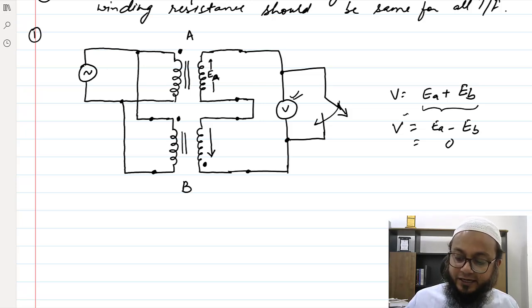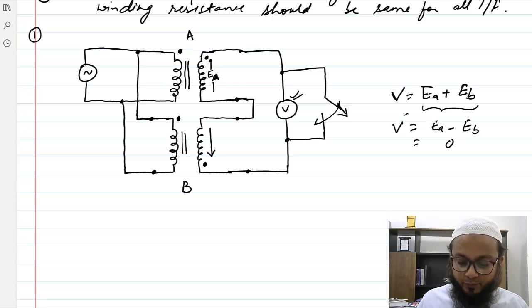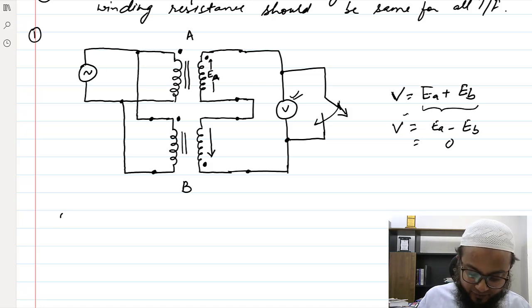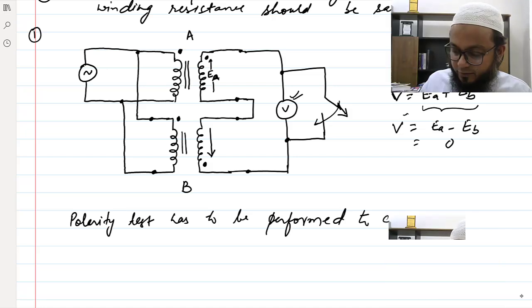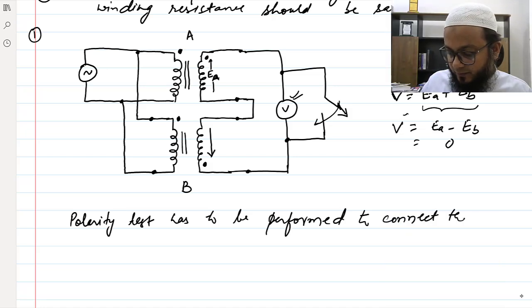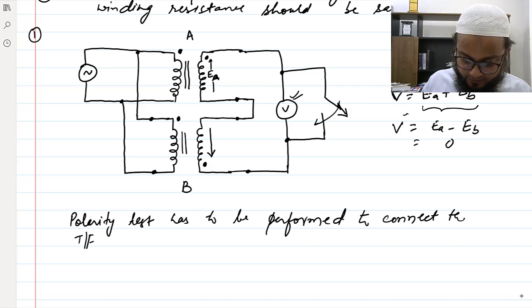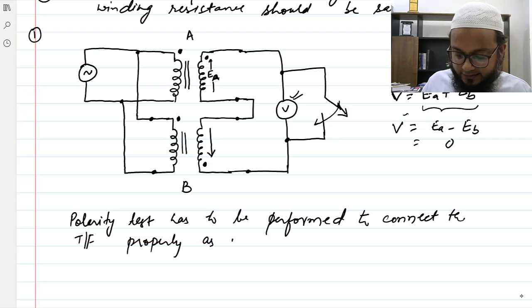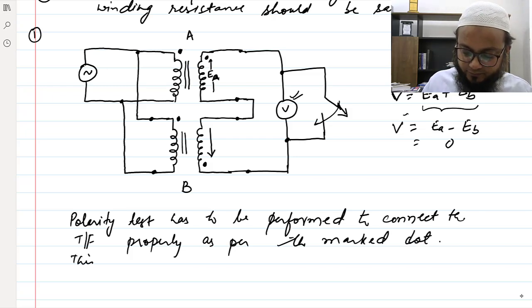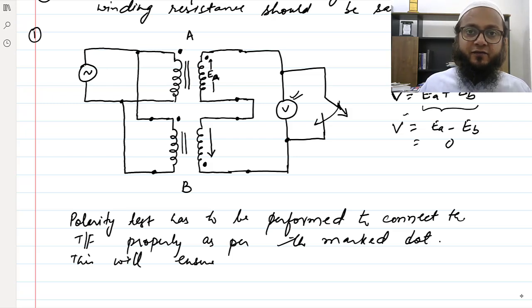Now you see how you will connect it to the load. Let's say your polarity has been marked now. So here for proper polarity, test has to be performed to connect the transformer properly as per the marked dot. So proper dot and equal voltage ratio will ensure zero circulating current.